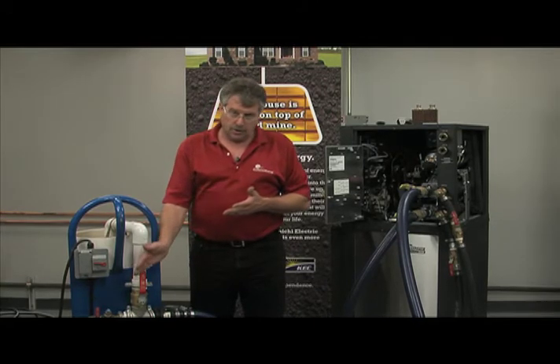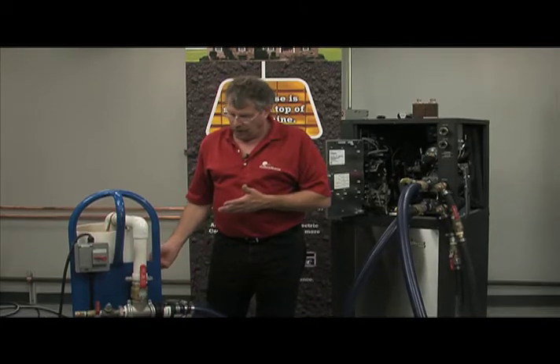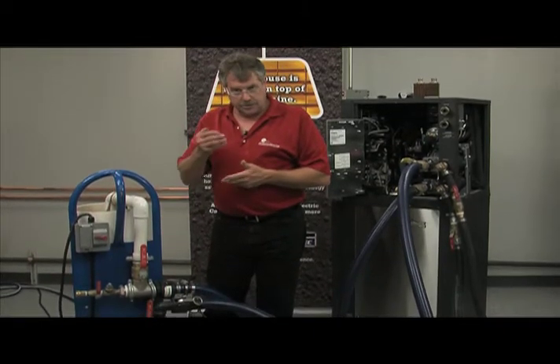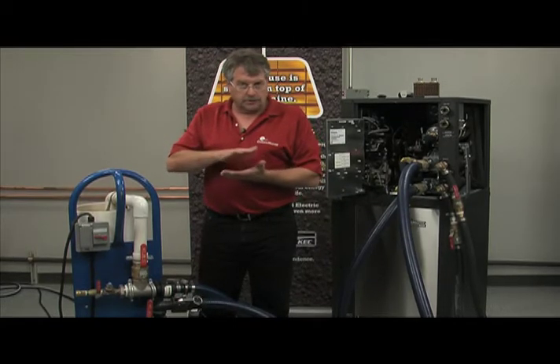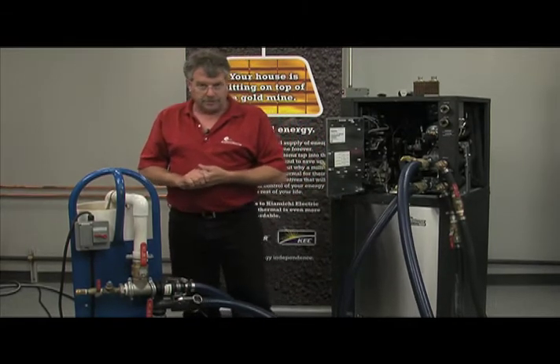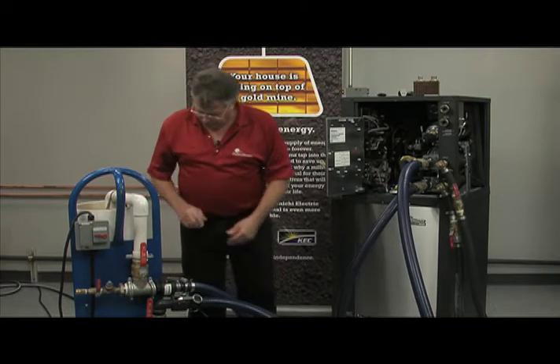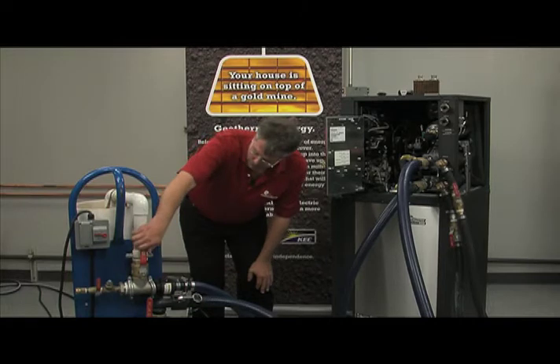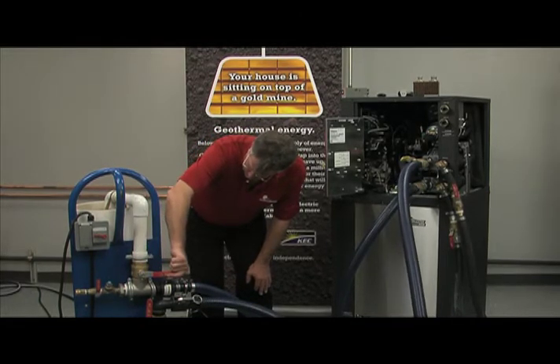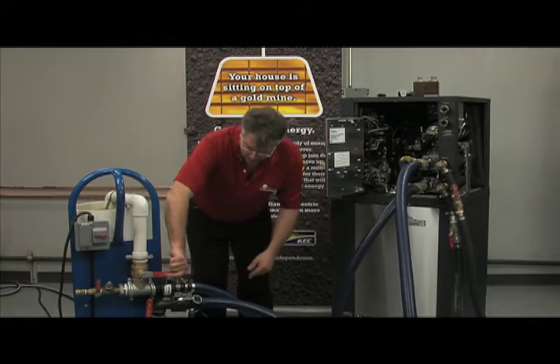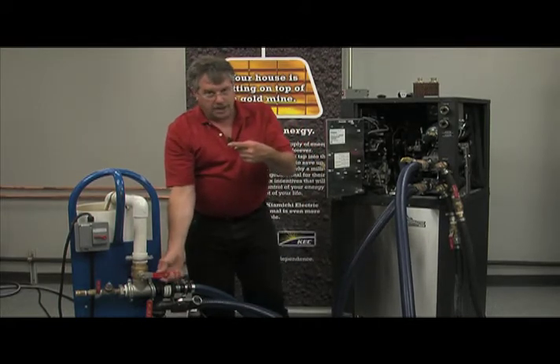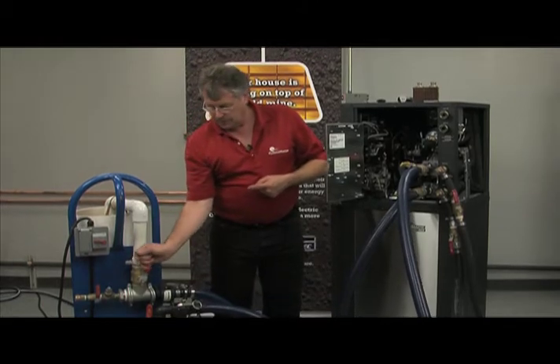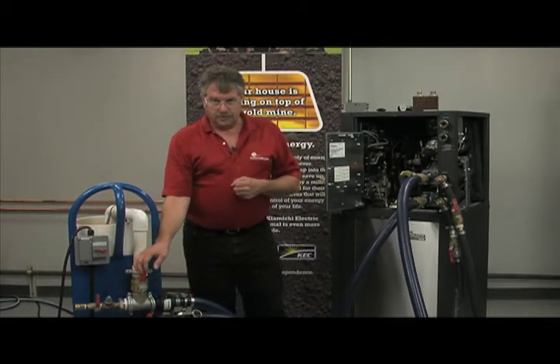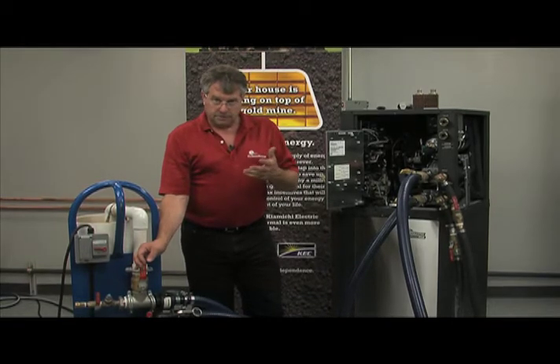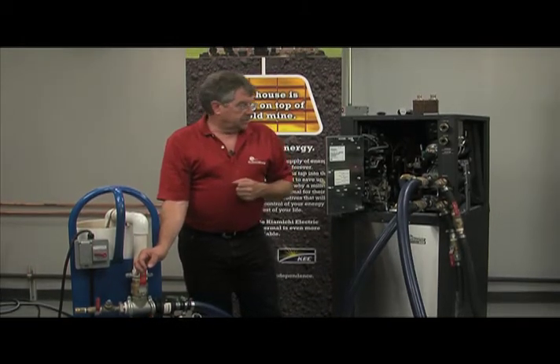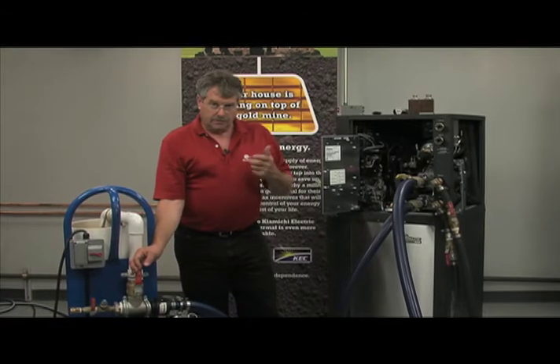So again, I'm going to close this return valve and I'm going to look at my fluid drop. I don't know if the camera will be able to see this. And I'm going to see if I have any air left in there, because air and gases compress, liquids do not. I do have a little bit of flex in my hoses here, which I will allow for. So I'm going to go ahead and set my fluid level, which it is. Deadhead that pump, and I'm experiencing a drop of about 3/8 of an inch, which is fairly satisfactory, to be honest with you. That or less, typically for most flush cart hoses and apparatuses, means that you've got that air out.